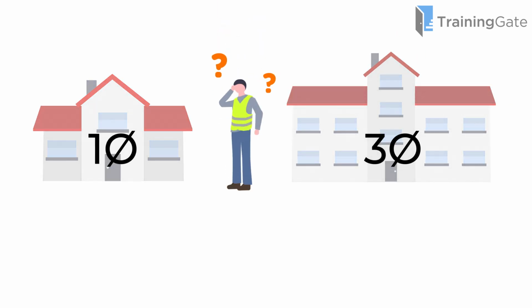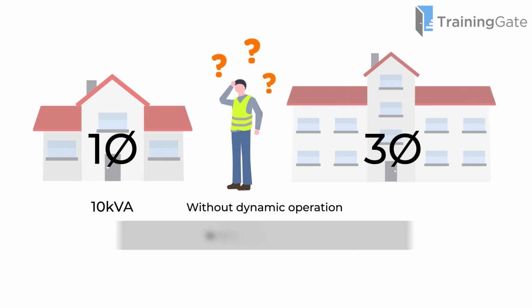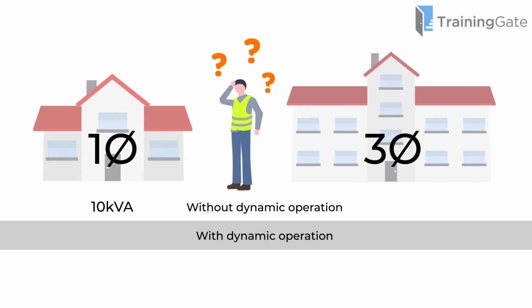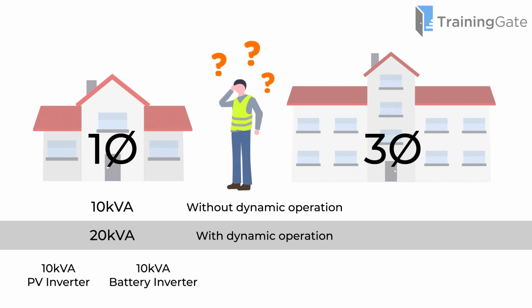For both single-phase and three-phase sites, the maximum inverter capacity per phase can be different depending on whether dynamic operation is enabled. In single-phase sites, the capacity is limited to 10 kVA per phase without dynamic operation, but with dynamic operation, this increases to a total of 20 kVA per phase, divided between 10 kVA for PV inverters and 10 kVA for energy storage system inverters.